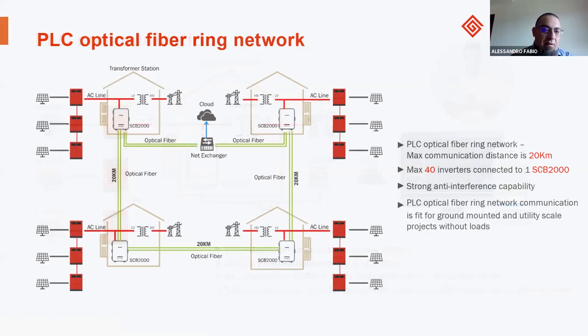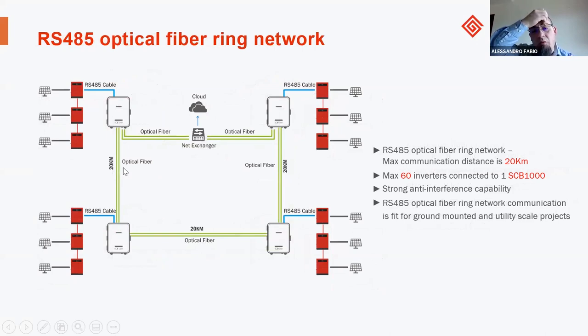Also with this option, the SCB-2000, we have the possibility to communicate with an optical fiber ring network, for example. The distance is longer, up to 20 kilometers. So it's really for large-scale systems, and you can arrange it with fiber optic components. Also optional is a ring network with SCB-1000. This is a monitoring system. You connect the SCB-1000 with the inverter through the RS-485 cable, but to connect the whole system, in this case, you can connect with fiber optic for a single SCB-1000. And so you can go to the cloud, to our SEMS portal, directly from the monitoring system.